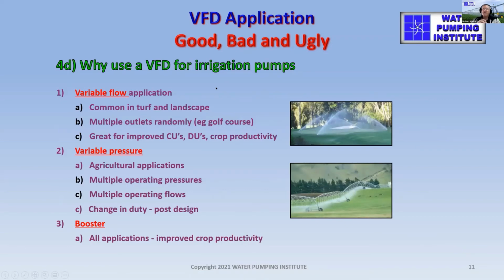Why use a VFD for irrigation pumps? Well, we might want to have variable flow, and this would be typically turf orientated. It's common in turf and landscape. We have multiple outlets randomly coming on, although they are programmed. And it's great for improved CUs and DUs and crop productivity, but it doesn't save much energy in a variable flow situation.